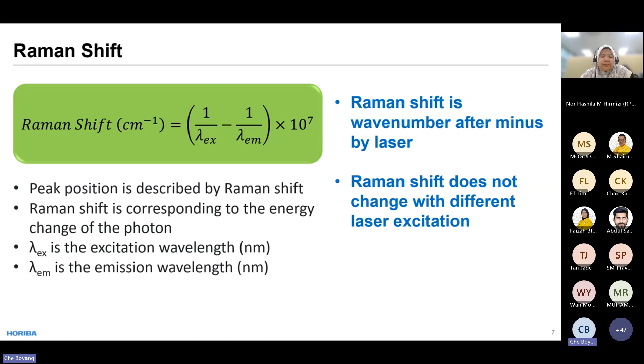Here is an example. If we use wavelength as the x-axis and test the same sample using three different lasers, blue, green, and red, then because they are at different wavelengths, your signal will also appear at different wavelengths according to the laser. If you use a 400-plus laser, your signal starts from 400 plus. If you use a 600-plus laser, it starts from 600 plus. Although the pattern is quite similar because it's the same molecule, the value of your x-axis is different.